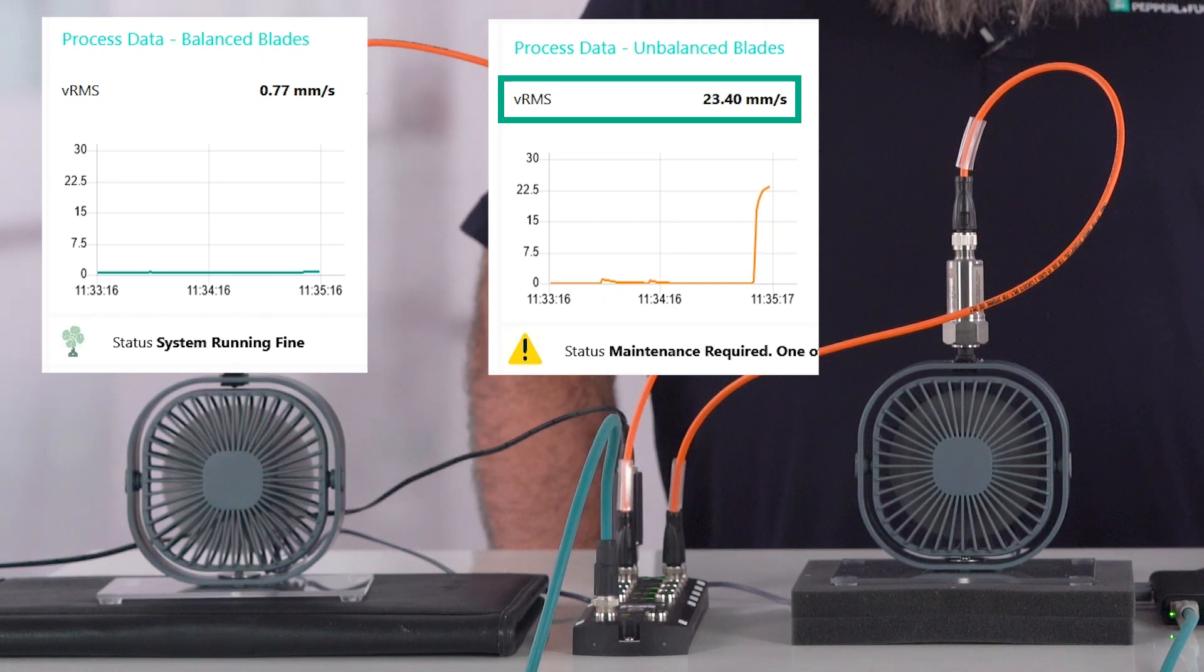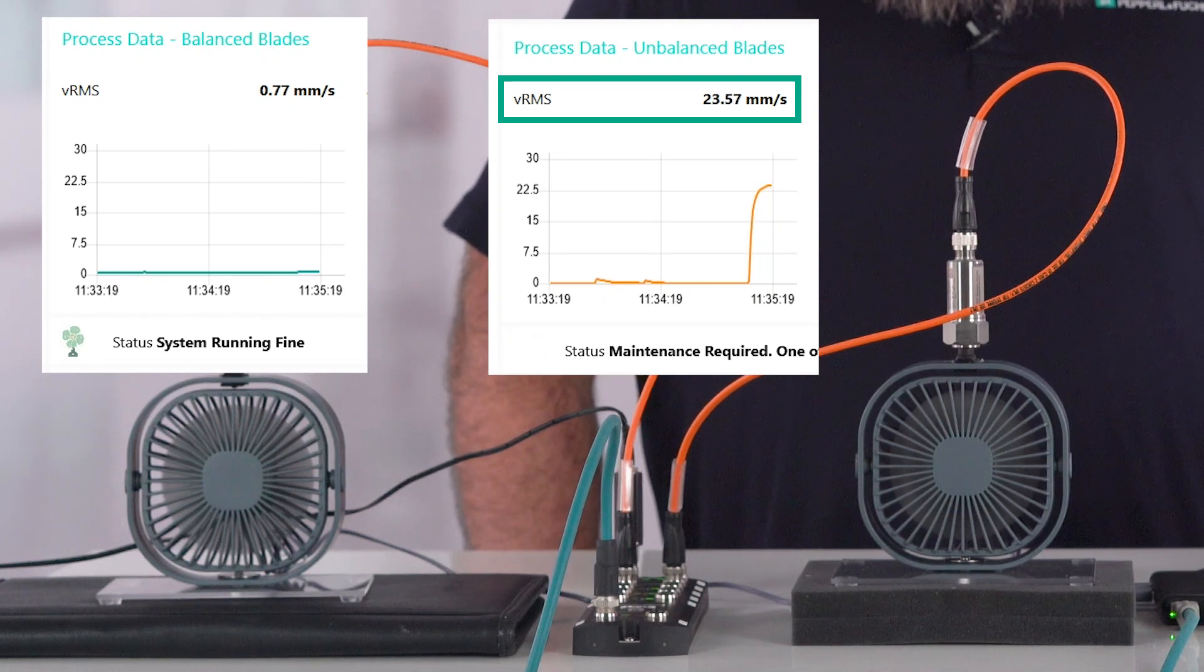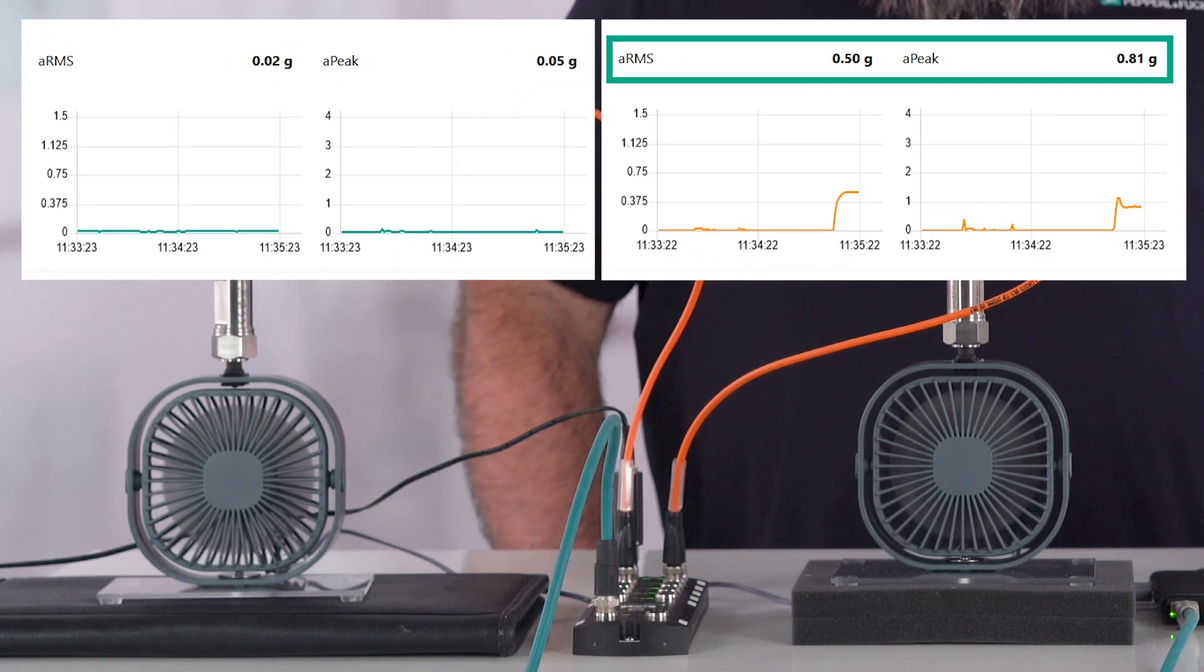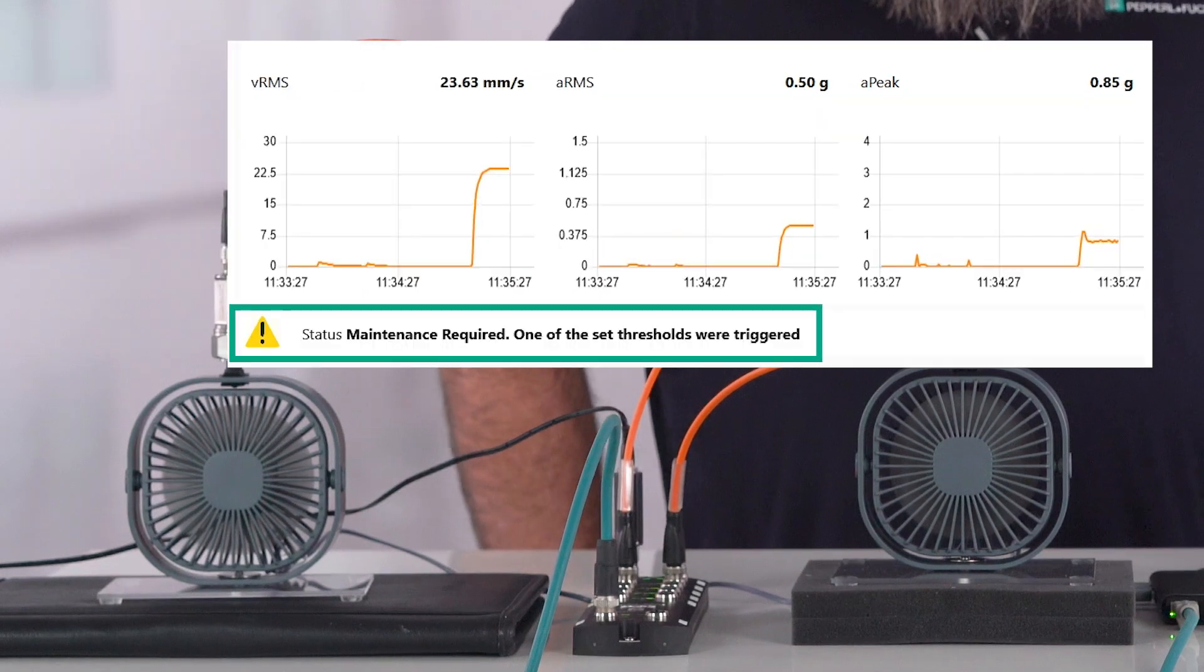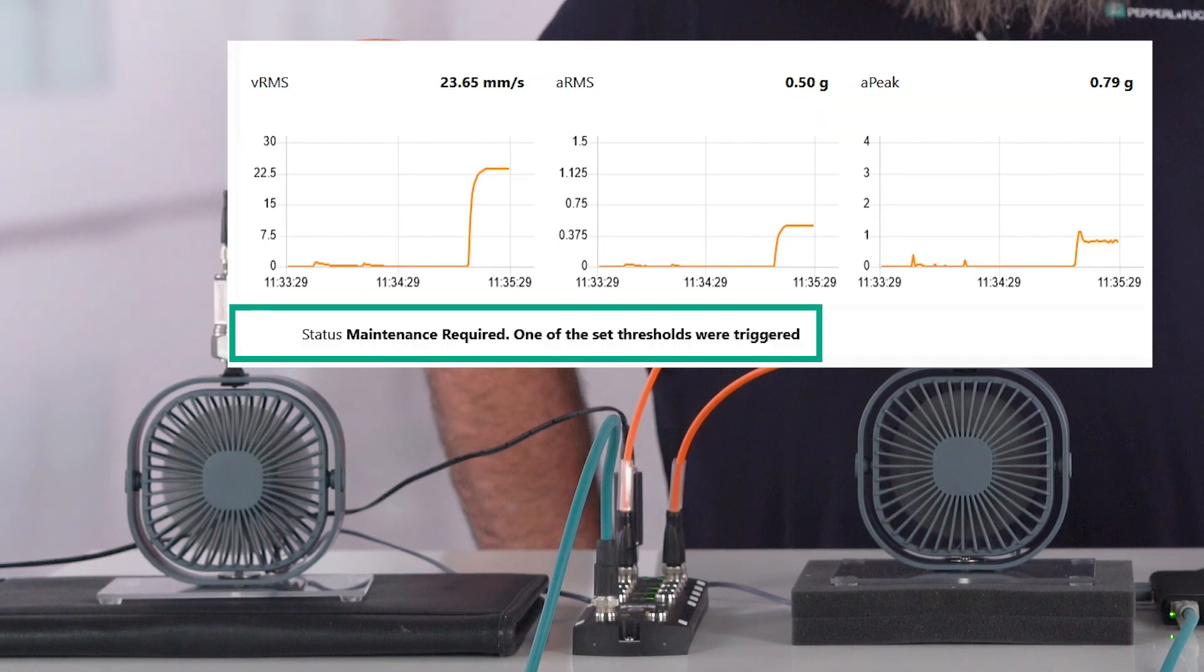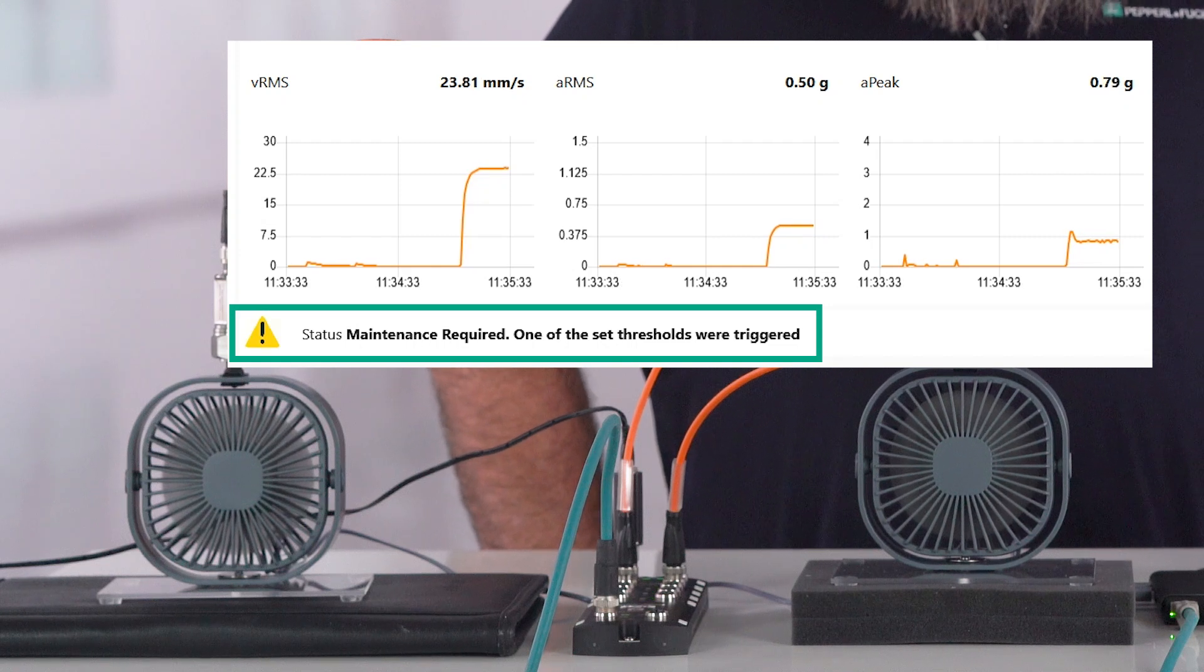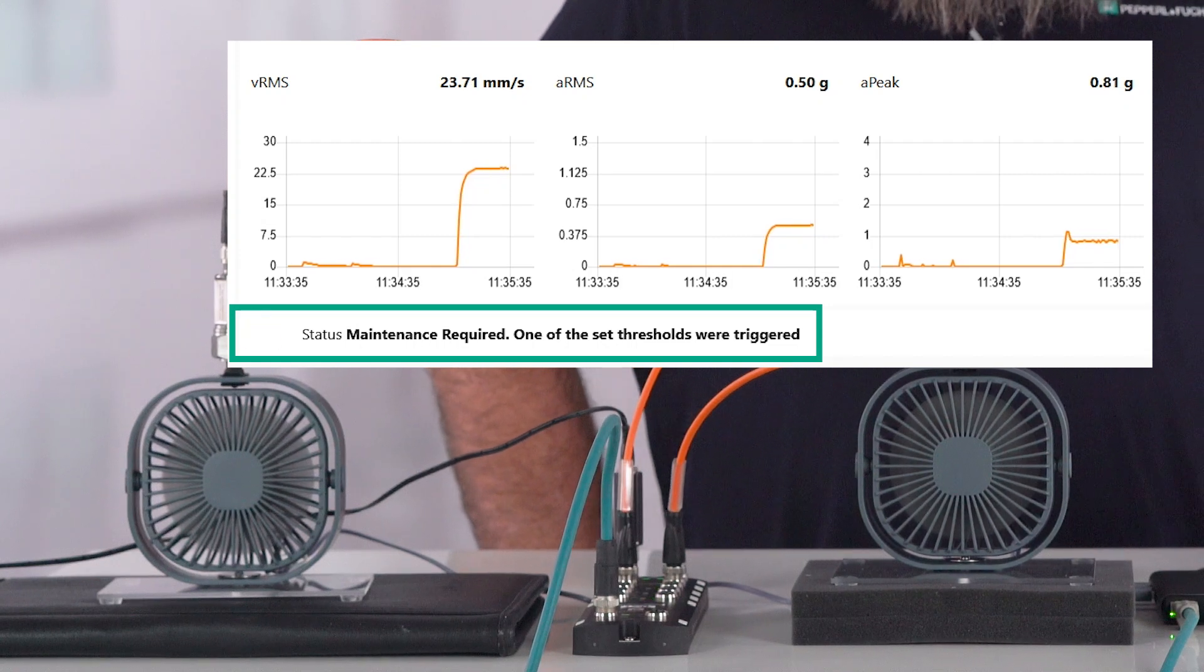Right away, you can see the fan is unbalanced because it has an RMS velocity that is much higher than Sensor 1. The acceleration RMS and peak values are also higher than Sensor 1, and the fan icon has changed into a warning icon. All of those indicators would tell an operator that the fan is in need of maintenance as the values are outside the normal operating parameters.